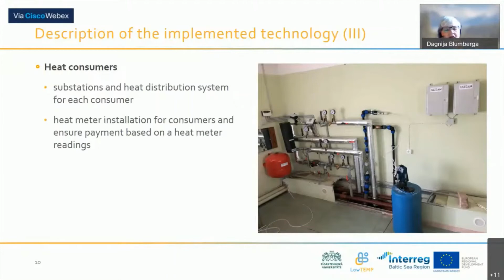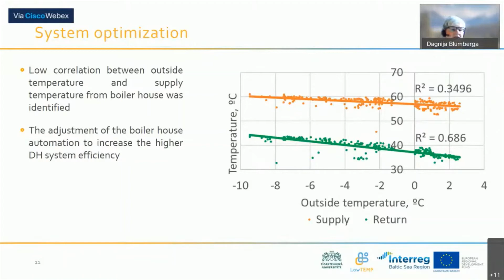This is the main picture showing monitoring data, and as you see, in reality we reached 60 to 30 or 35 to 45, depending on outdoor temperature. When we show this graph to other district heating enterprise representatives, they always look and ask, is it possible? This pilot project is a real pilot project, and it shows that it is possible to reach such temperature levels, not higher than 65 degrees, in district heating pipes. Next slide, please.